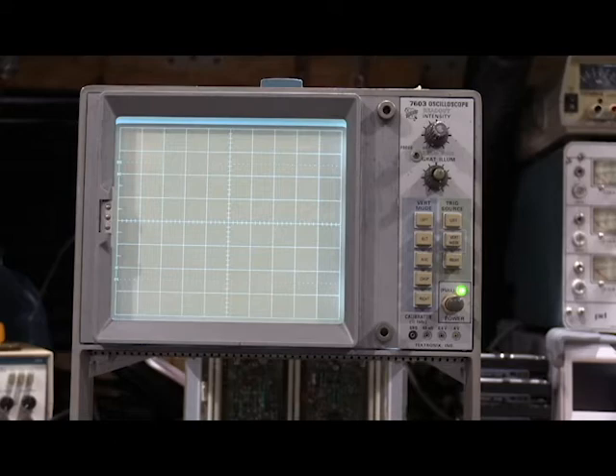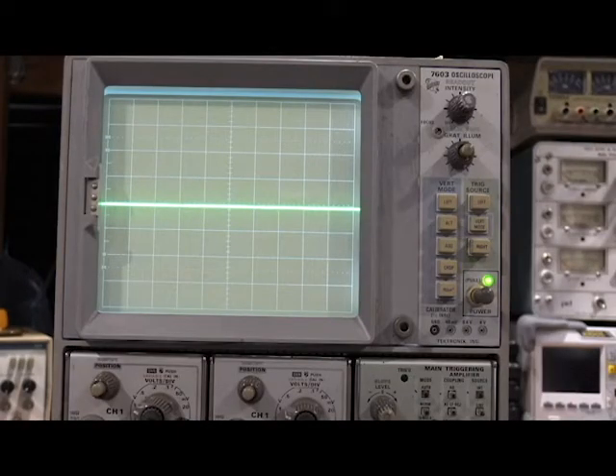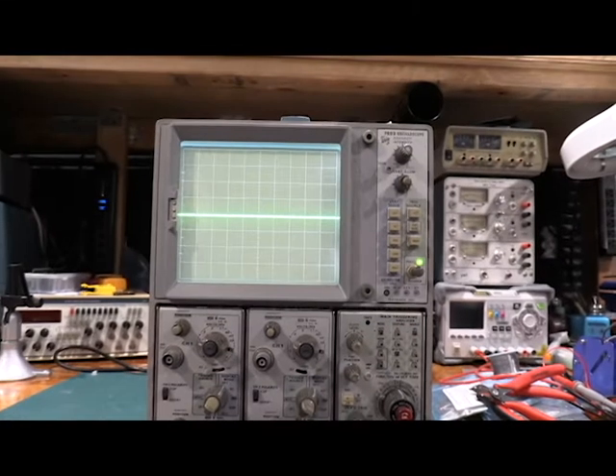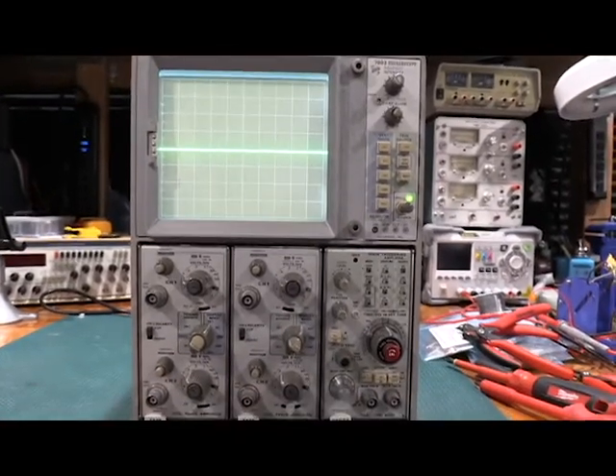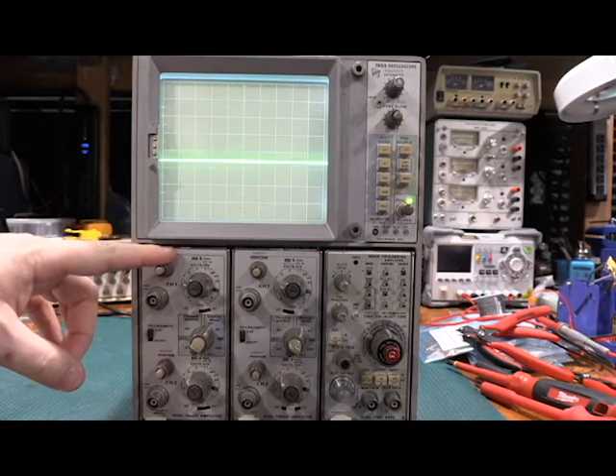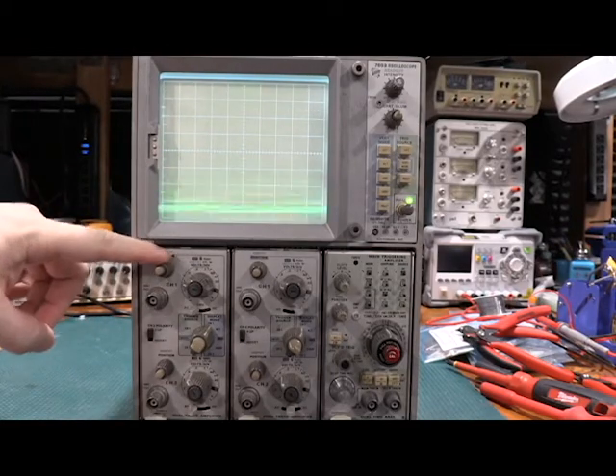So what I'm going to do now is pull up the service manual for the 7603, and I'm going to start going through the calibration process for the frame. That's not going to give me a working scope. To do one of these modular scopes, you have to do the frame, you have to do the vertical, and you have to do the horizontal. What I've done so far is set the controls up for the preliminary settings of the service manual. So to not torture the tube, I'm going to roll this off because it wants a 20-minute warm-up.